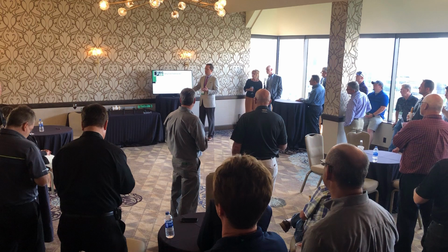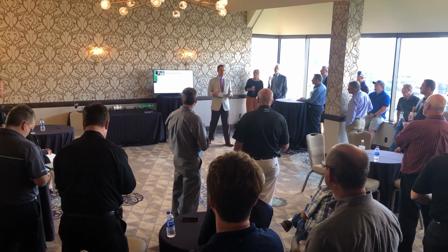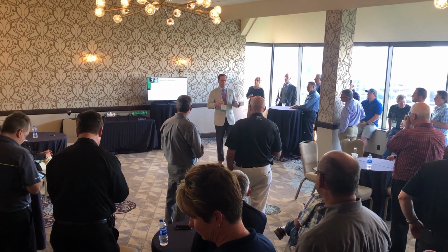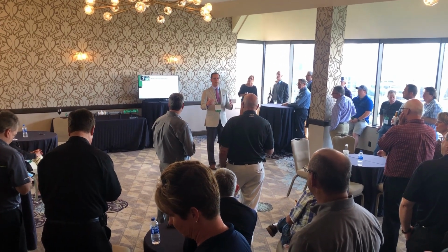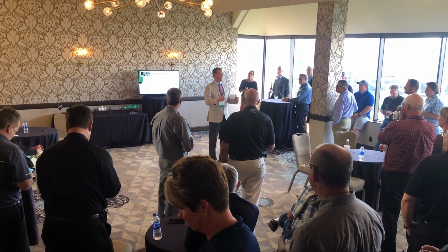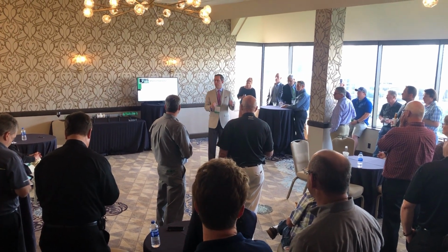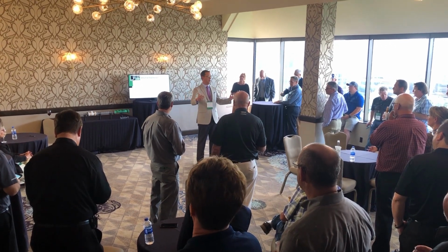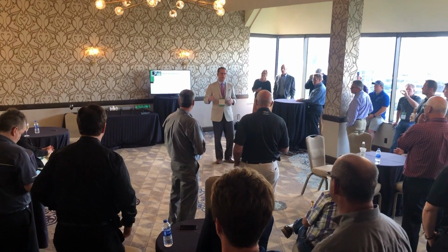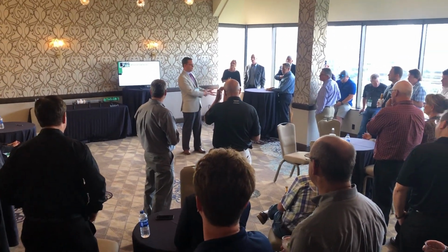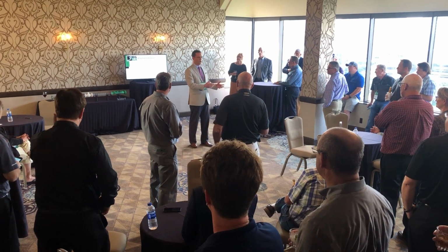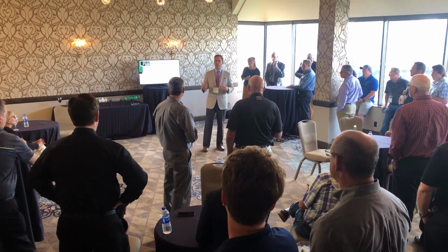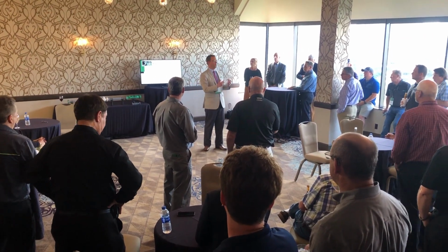So I'm using this word end treatment. First, let me just describe what end treatments are and why they exist. For a lot of the folks that are here who are involved in measurement, the measurement supervisors don't necessarily have jurisdiction regarding the geometry of the piping that's coming into the measurement station. So what happens is, as we understand in our world, there are tons of installation effects that can wreak havoc on a meter. And if you don't have jurisdiction on whether it's 3 elbows in plane, out of plane, 2 elbows, whatnot, all you have is jurisdiction over this square footprint, then each end user takes it upon themselves to come up with an end treatment design.